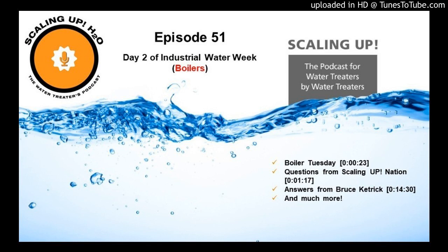Another thing that people do is they'll have 2 boilers, so one can go offline and they'll have another one as a backup. And typically they'll run both in a lead and lag situation. That means one's coming on while the other one's waiting to see if it needs more demand, and that's when it will come on. Well, depending on how they set this up, sometimes they never put the lower used boiler in the number 1 position and vice versa. And the boiler that's not getting used, I guarantee you, will corrode faster than the boiler that is getting used.